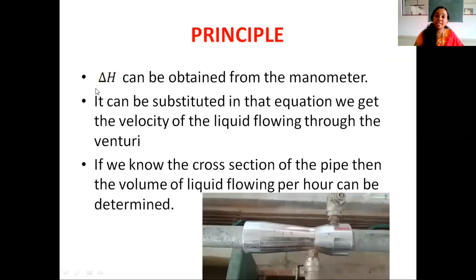If we know the pressure head, we can substitute this value in the equation and find the velocity of the fluid passing through the pipeline. If we also know the cross-section of the pipeline, then we can easily find the flow rate and determine the amount of liquid passing through the pipeline. This is the principle involved in Venturi meter.